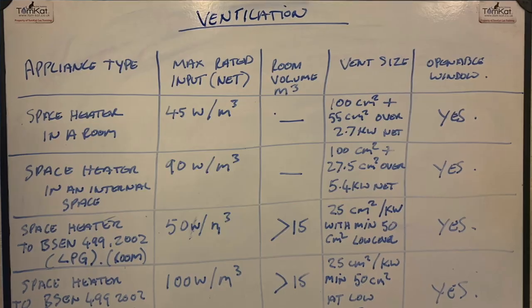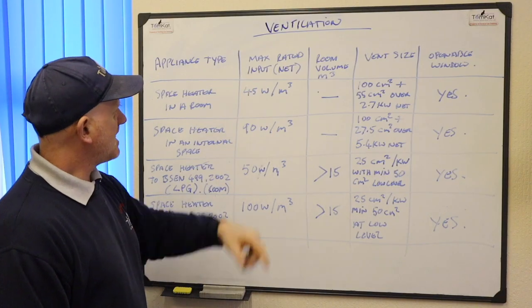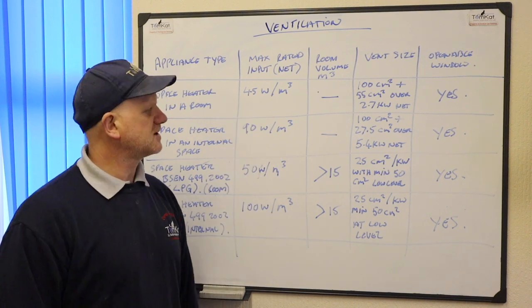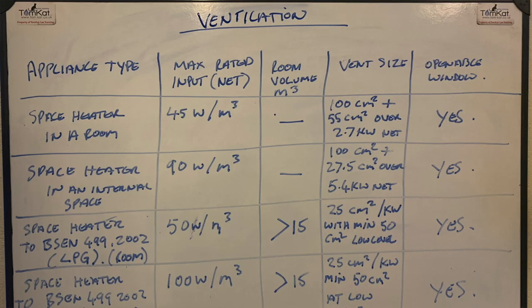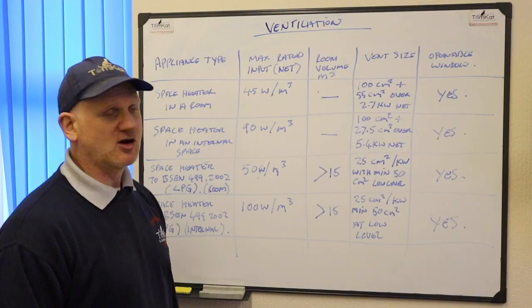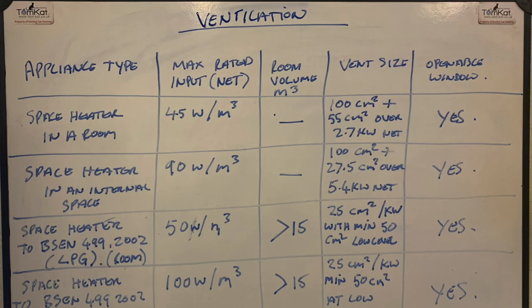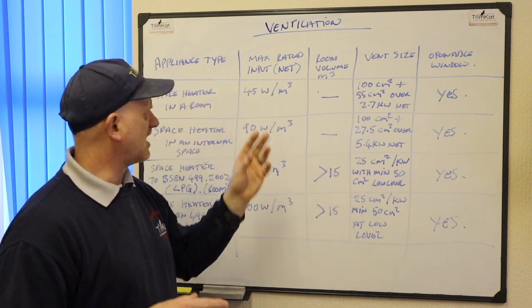For a space heater in a room — a living room or dining room — the maximum rated input in net kilowatts is 45 watts per metres cubed. The room volume column shows a dash because we're working to the 45 watts per metres cubed figure. The vent size required is 100 centimetres squared plus 55 centimetres squared for every kilowatt over 2.7 kilowatts net, plus an openable window.